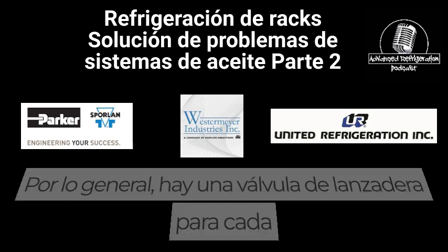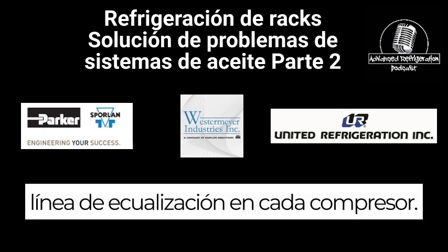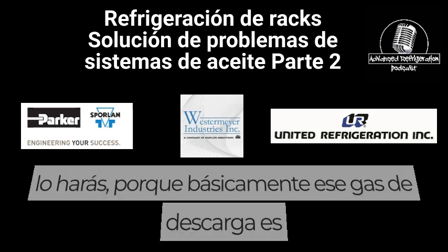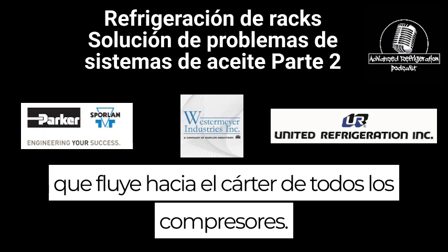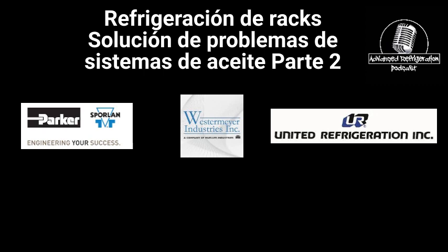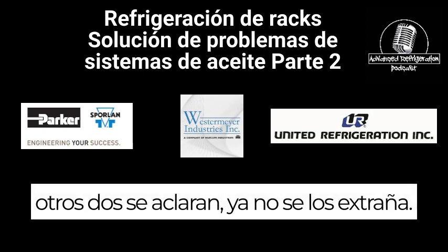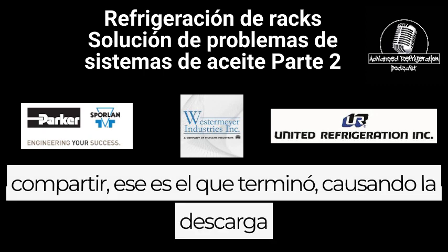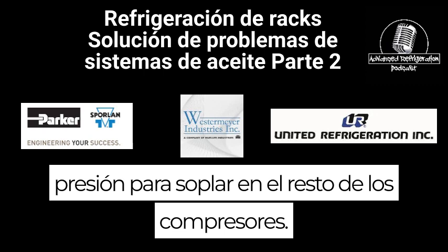Looking for the misting. There's usually a shutoff valve for each equalization line on every single compressor. So if you see misting in all three, which you will, because that discharge gas is blowing into the crankcase of all the compressors. If you shut off one equalization line and the other two clear up, they're not misting anymore, then the one that you just shut off that was sharing is the one that ended up causing the discharge pressure to blow into all the rest of the compressors.